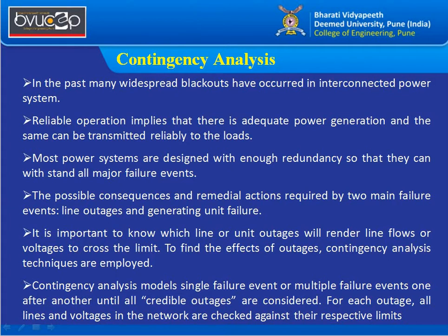So whether the remaining generators are going to cope with the demand for electricity required? If yes, then how much is the power flowing through all lines, whether they are within the limits or the voltages are getting violated? So that is the importance of this contingency analysis that is applicable during the planning stage, to understand whether the system is going to be stable, reliable, and it is not going to collapse and go into blackout.